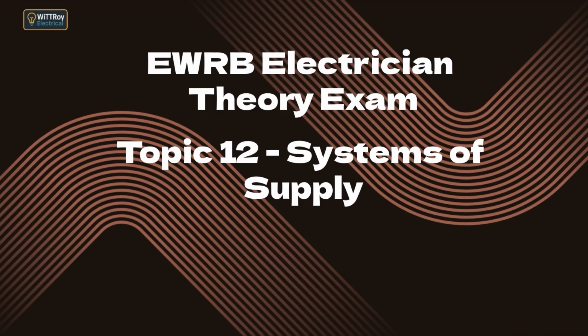Summary. New Zealand supplies start from 11 to 18 kV generation, then step up to 110 or 220 kV for transmission, and step down to 33 kV and 11 kV for distribution. Our three-phase, four-wire system gives 400 volts between phases and 230 volts from phase to neutral.